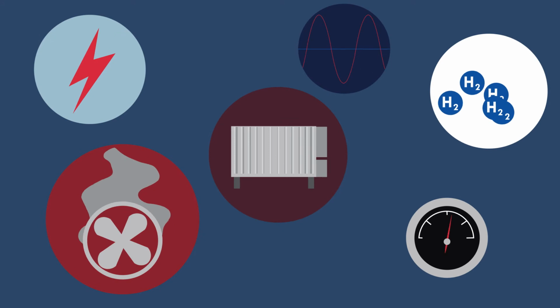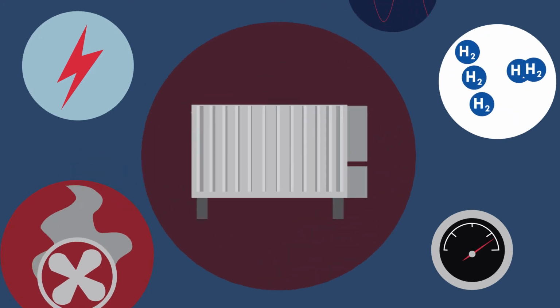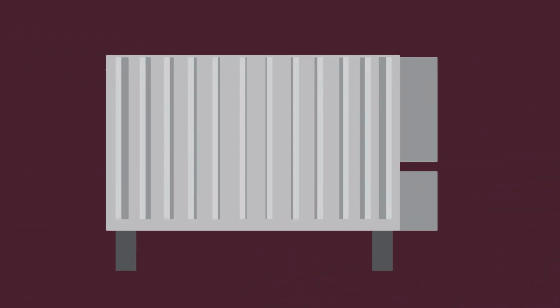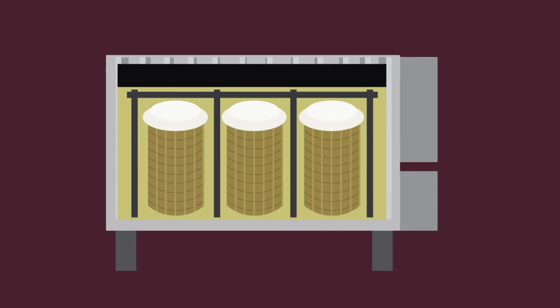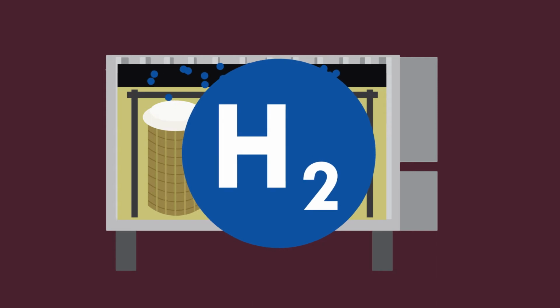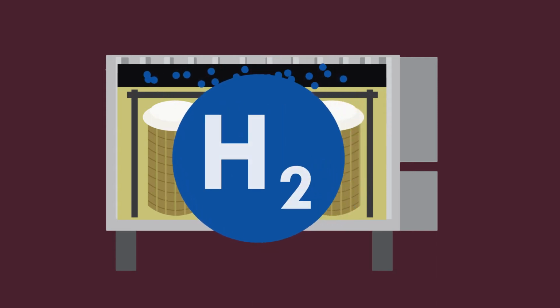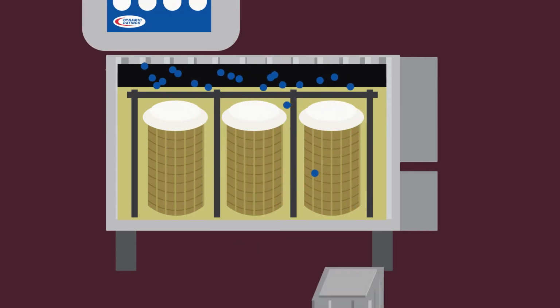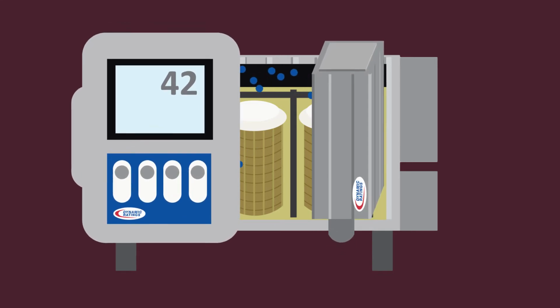Monitoring systems will alarm on a variety of different things. One important element to monitor is the presence of gases generating in the transformer. If there is a developing fault in a transformer, gases generate at a rate which typically allows them to remain dissolved in the oil. Hydrogen is the first fault gas to be generated and is used to alert that there is a problem that needs attention. Key gas hydrogen sensors are available in several designs.